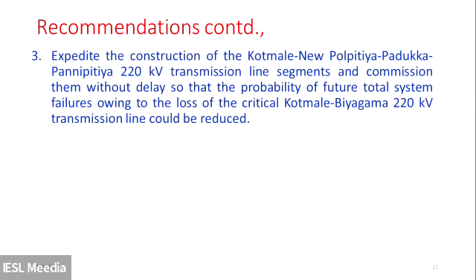And then our load flow studies reveal that in this scenario, when Kothmale-Biyagama circuit 1 and 2 both are gone, even the new Anuradhapura circuit 1 and 2 could not have saved it. However, if we had commissioned the Kothmale, New Polpitiya and Padukka Pannipitiya 220 kV line, and if that was available, then the system could have been saved. But unfortunately, when the incident took place, that line was not available. I don't know whether that is there now.